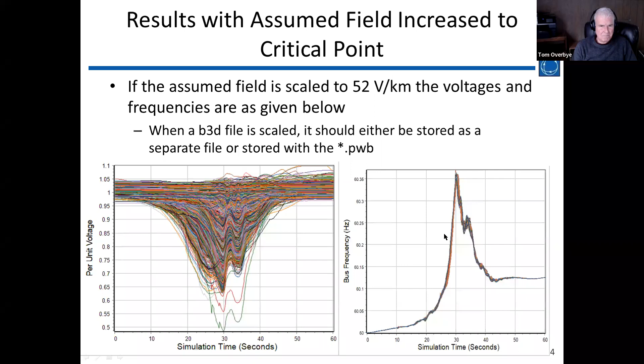This is the frequency variation, and again I can look at full details here. I took that more stressed situation and asked what's going on in terms of the grid at that point in time. I contoured my voltages at 30 seconds, which was easy to do because I had saved the power flow states. I should note I changed the contour scaling, so 0.7 is now dark red. This is a very stressed electric grid at this point in time, but you can see the stress is localized to this area. The rest of the grid is in fairly good shape.